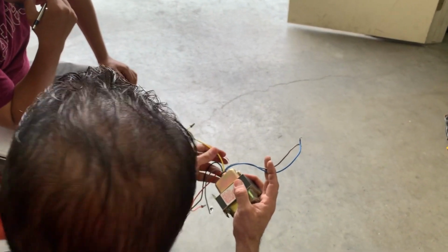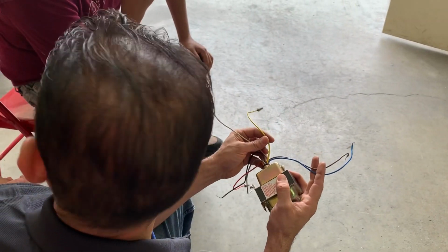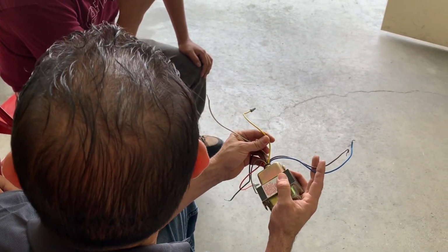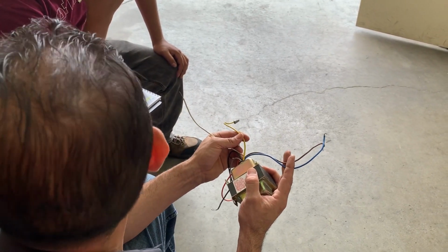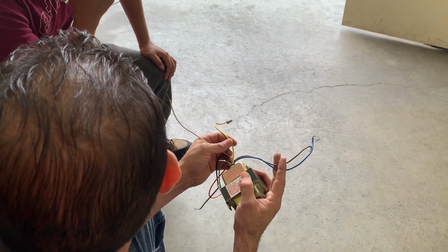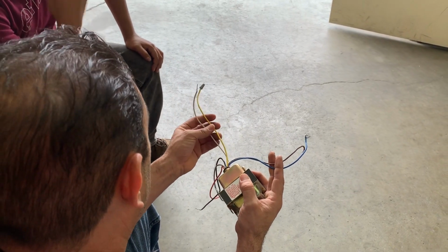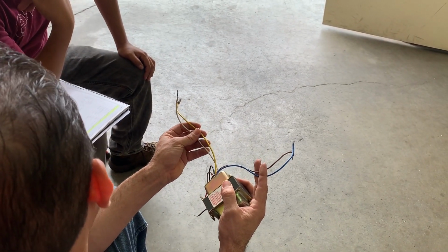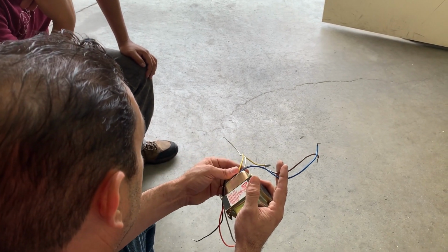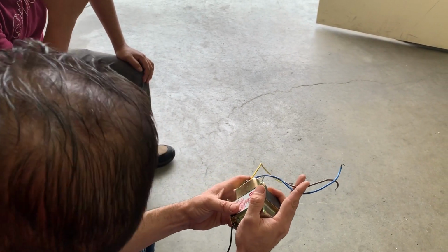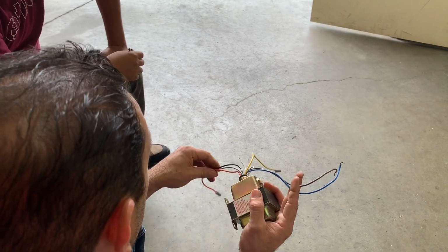No, you're not. You're going to get who knows what. But you have to have 24 volts or it will not turn the equipment on. If you're at 18 volts, it won't work. If you're even at 21, 22, it probably won't work. And you don't want to go above 28 or 29 because then you might burn out a circuit board.